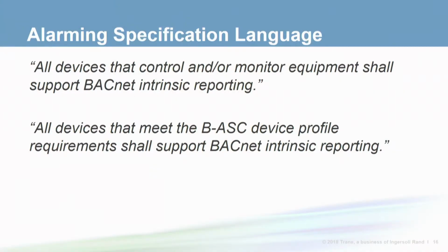Many vendors choose to also include intrinsic alarming support in their ASC profile devices because it's such a common requirement in the marketplace. So if you want support for alarming, don't discount ASC devices out of hand. When you're writing a specification, just be sure to require intrinsic alarming support. This slide shows 2 examples of spec language that you could use.